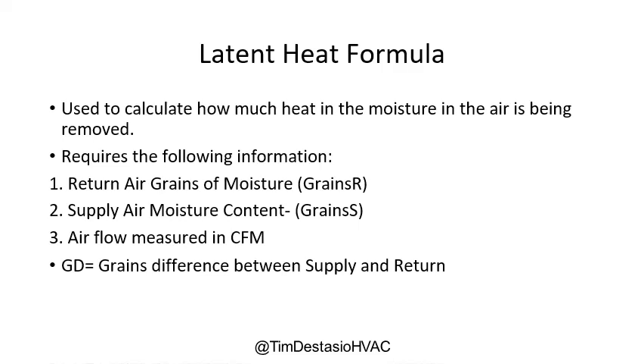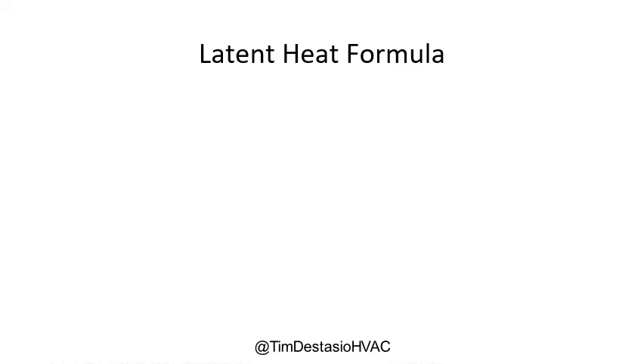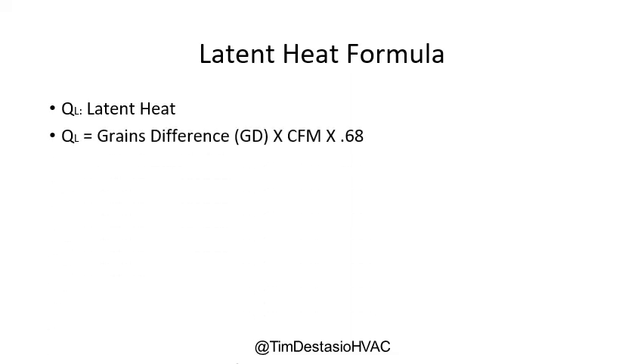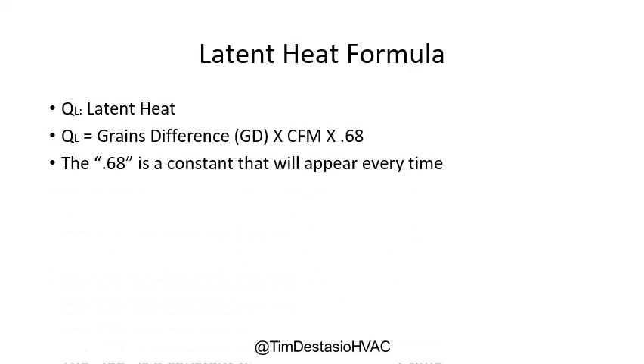It's a similar concept to the sensible heat formula. Instead of dry bulb temperature difference, this time we're looking at grains of moisture difference between supply and return. Here's our formula: Q sub L equals grains difference times CFMs times a constant of 0.68. Just like the sensible heat formula had a constant that appears every time, so does the latent heat formula — only this time it's 0.68.